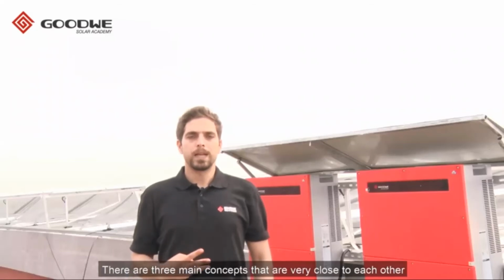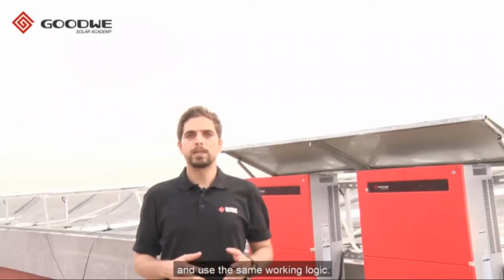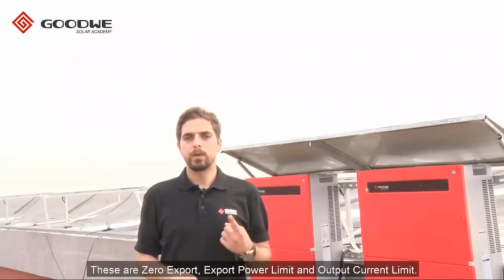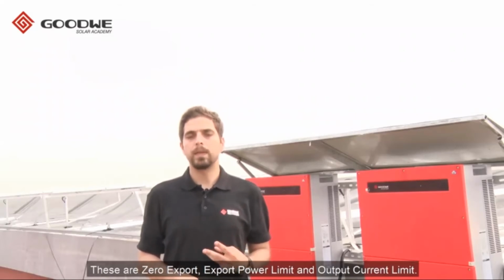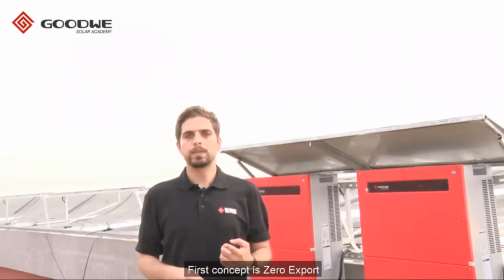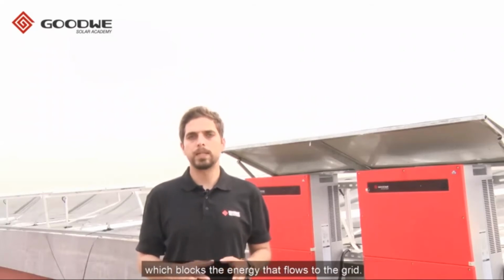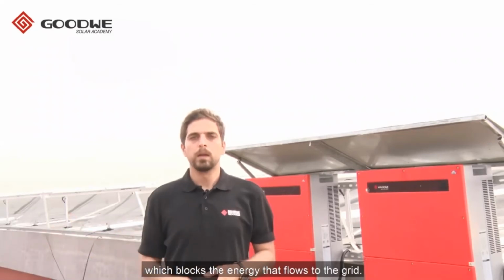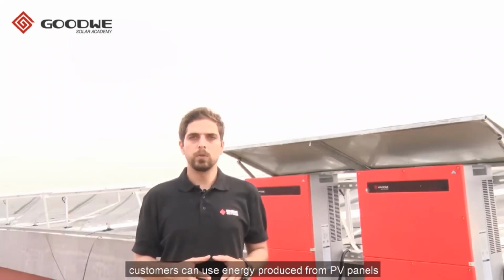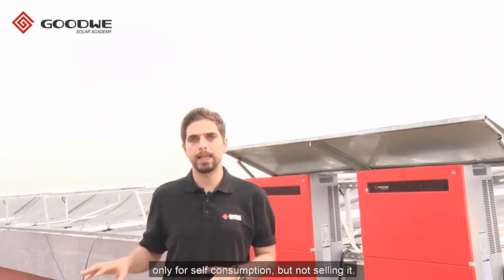There are three main concepts that are very close to each other and use the same working logic. These are zero export, export power limit, and output current limit. First concept is zero export, which blocks the energy that flows to the grid. With that feature, customer can use the energy produced from the PV panels only for self-consumption, but not selling it.